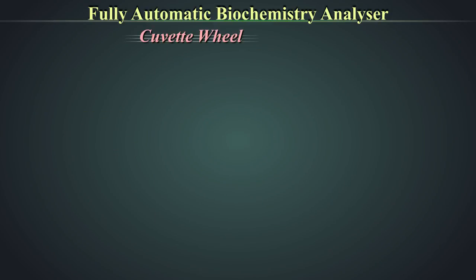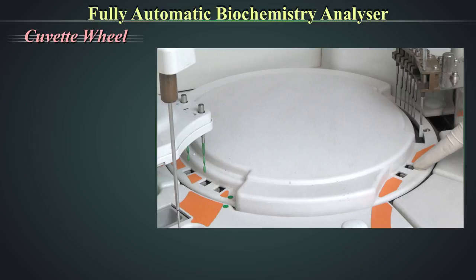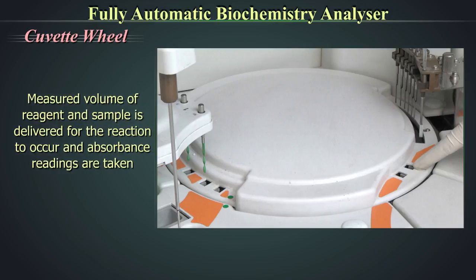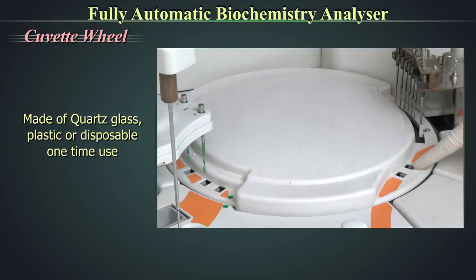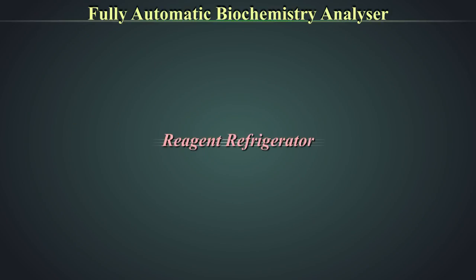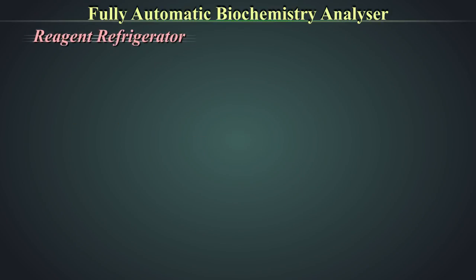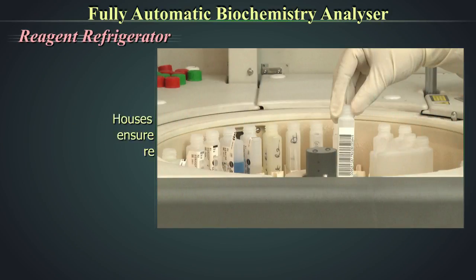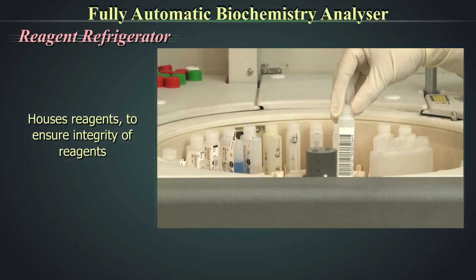The cuvette wheel houses glass cuvettes where measured volumes of reagent and sample are delivered for reaction to occur and absorbance readings are taken. The cuvettes are made of quartz glass, plastic, or disposable one-time use material.